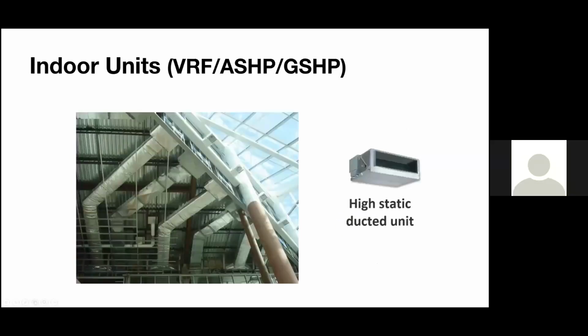Then there's an option for high static ducted units. These are typically used for when you think, hey, I have a lot of capacity that I need to bring in. I need a lot of CFM. Why don't we take one of these ducted units? A perfect application would be a large lobby space, a pretty open room, or maybe even an auditorium. I've used that in a couple scenarios, but this has a little bit more static pressure than the medium static. It's up to 1 inch. A little bit larger, but this does get the job done if you want more capacity, anywhere from 6 to 8 tons at the maximum end.